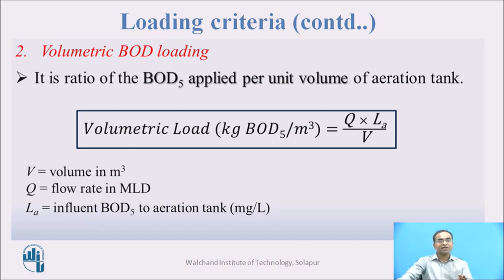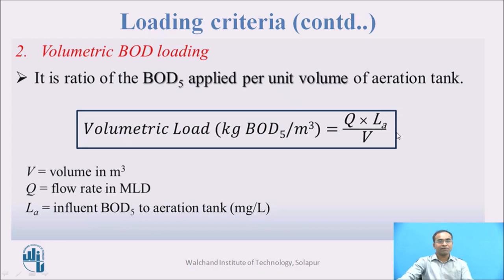The carbonaceous matter and its quantity will give us proper formation of microorganisms and secondarily activated microorganisms. That's why we calculate how much BOD to add. First, we calculate by experimentation how much BOD is present in the wastewater, termed as LA, measured in mg per liter. It is multiplied by the flow rate of wastewater and divided by volume of aeration tank. This formula gives us volumetric load in terms of kg BOD5 per meter cube.